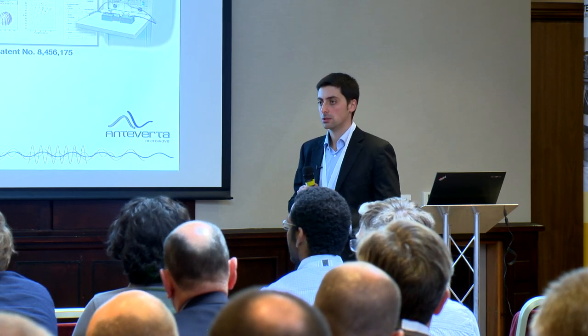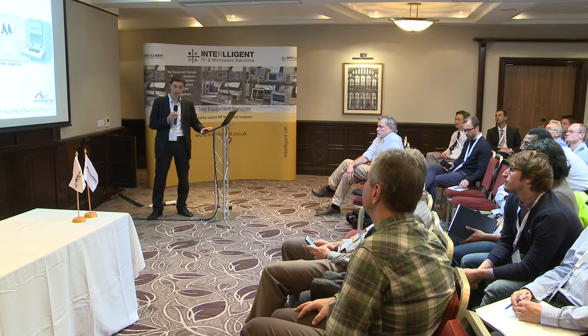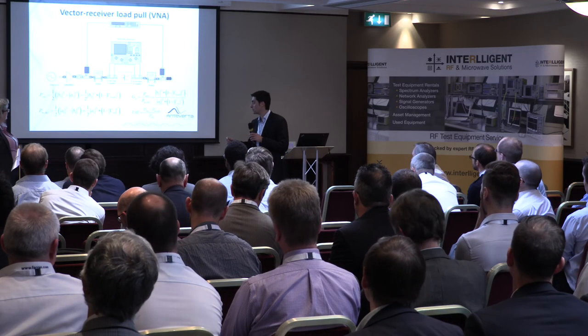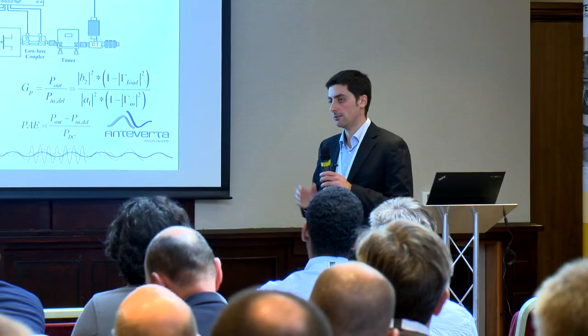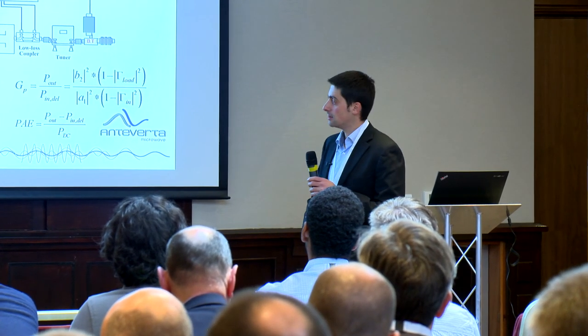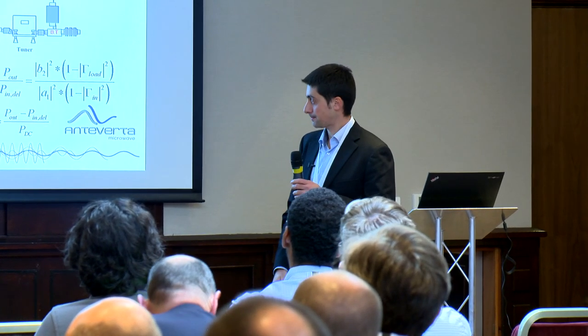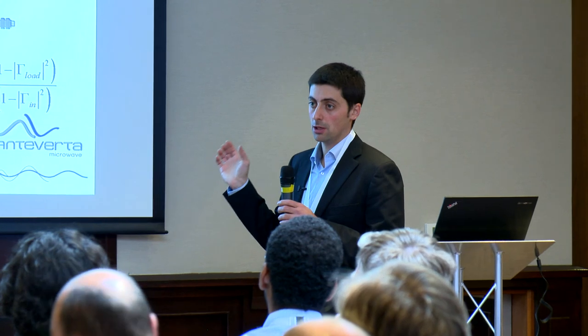Is the calibration routine the same for the polyharmonic? Yeah. Same calibration. So normally in a vector receiver system, that's this one, you start with a normal two-port calibration of VNAs, so SOLT or TRL calibration at the device reference plane. You have a power calibration in order to measure absolute power. And to measure time domain voltage and current, you have a phase calibration. So you use a phase reference device. I forget about how they call it. Phase reference device. So yeah.